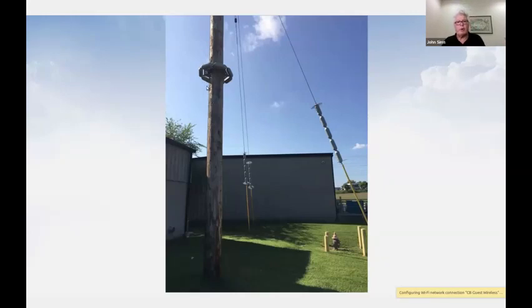It's fine. You see a pole there and some guy wires -- another example of how pole guard and line guard can be worked in unison. In this case, a unique thing: this is a water utility, and they had serious problems here. You'll notice they put line guard on the guy wires. Normally we'd think of a horizontal wire, but in this case, whatever slope those are, maybe 30 degrees, you're looking at line guard mounted over or above the traditional guy guards, which are like a split loom. The challenge with long rollers like guy guards is if there's any friction on the line at all, even a loose wire, that long loom won't spin -- which is exactly what was happening here.